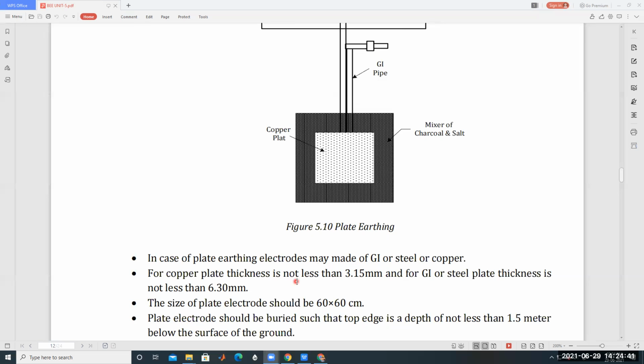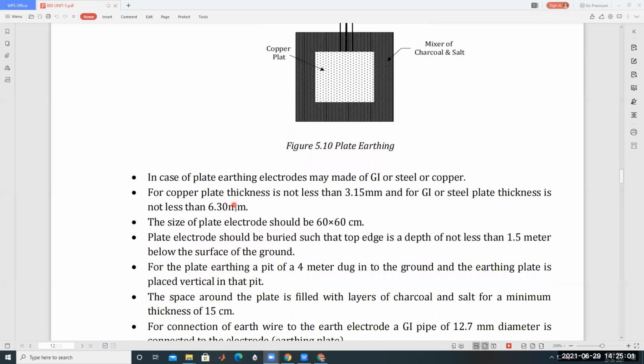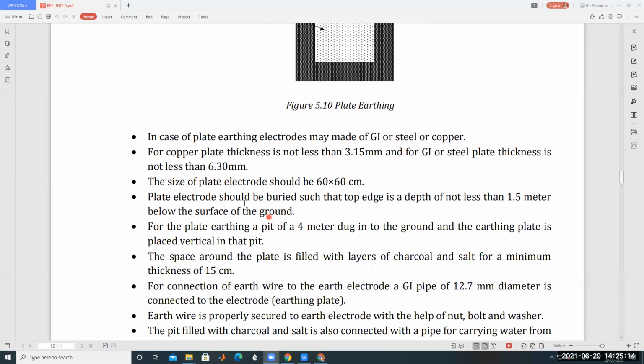For copper plate, thickness is not less than 3.15 mm, and for GI or steel plate, thickness is not less than 6.3 mm. So we have to maintain the thickness of the plates. For copper plates, the thickness is not less than 3.15 mm, and for GI or steel plates, not less than 6.30 mm.